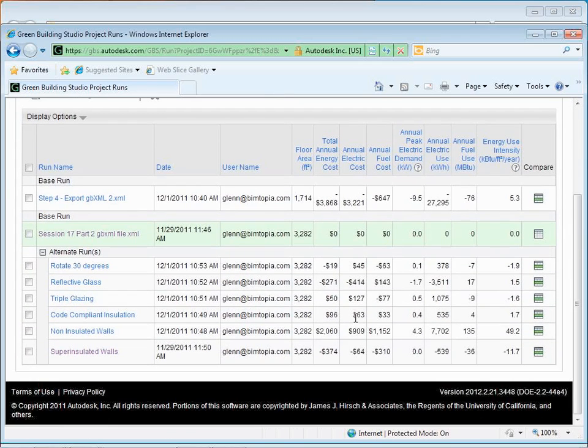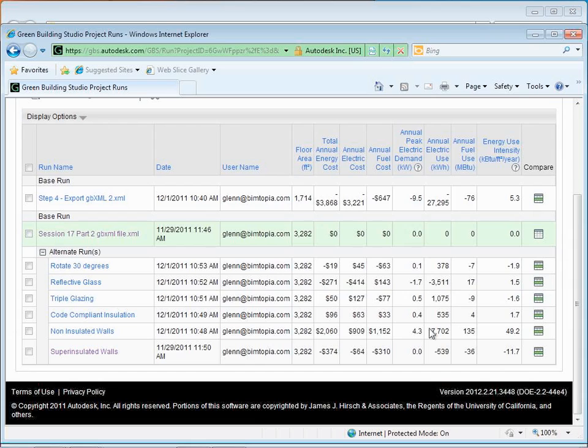If you look at the whole issue of the glazing and compare that back to the base assumption, I think the base assumption was double-insulated glass. So triple-glazing, it looks like it actually lowered it some, just a little bit, 1.6. So honestly, if I was comparing right now the choice of putting in triple-glazing throughout the whole window or super-insulating the walls, insulating the walls seems to be a better choice than increasing the glazing on the windows. Reflective glass, what's happening over there? Actually, there it's increasing a little. So we'd have to start thinking about that. It's interesting. The reflective glass is lowering the electric cost quite a bit. I'd expect that. We don't have nearly as much of an air conditioning load. But it's actually increasing the heating load because we're reflecting out the heat during the wintertime, so we're not getting that.